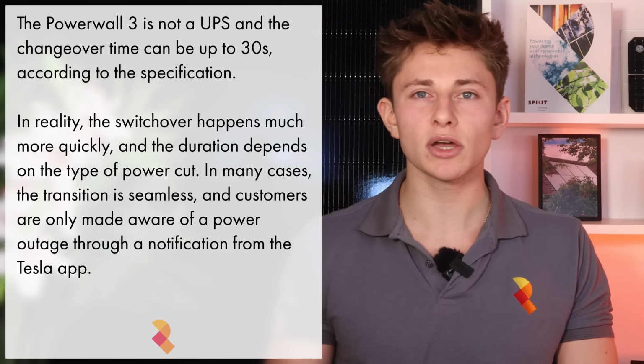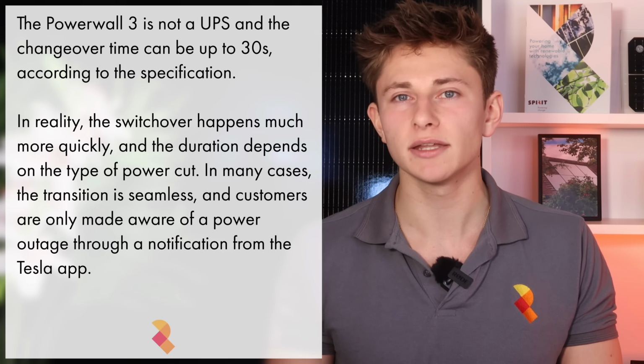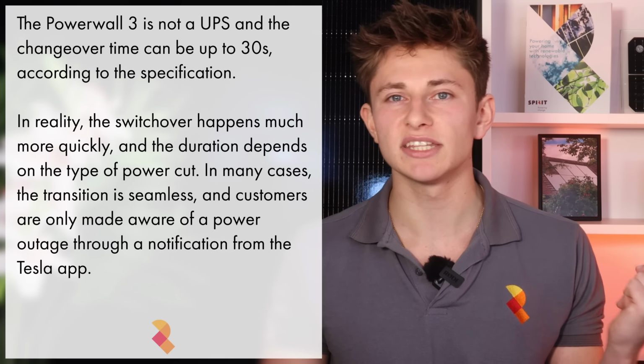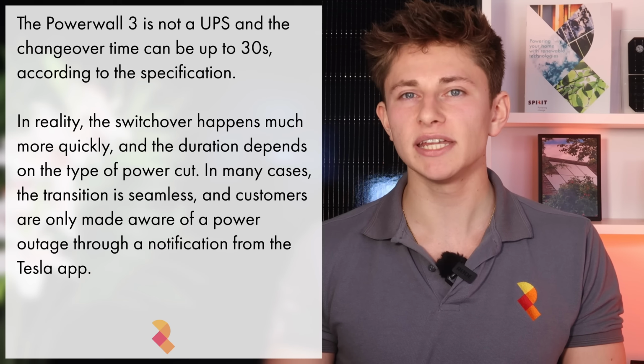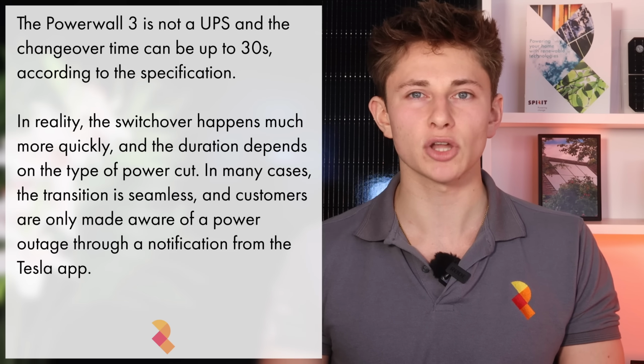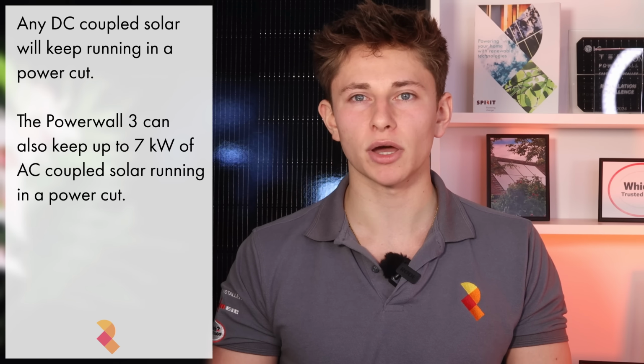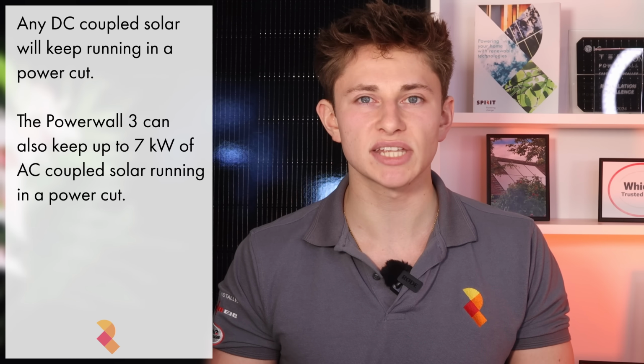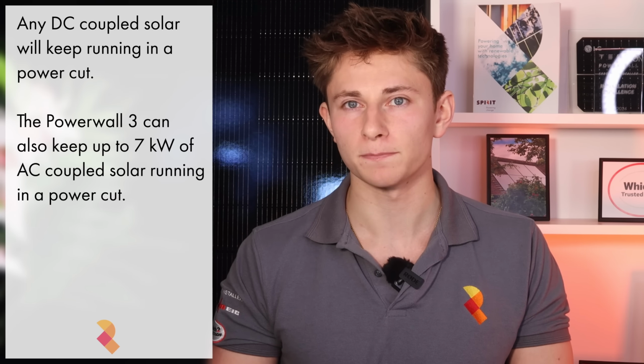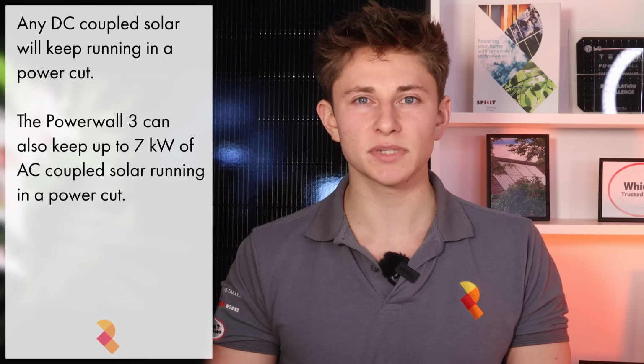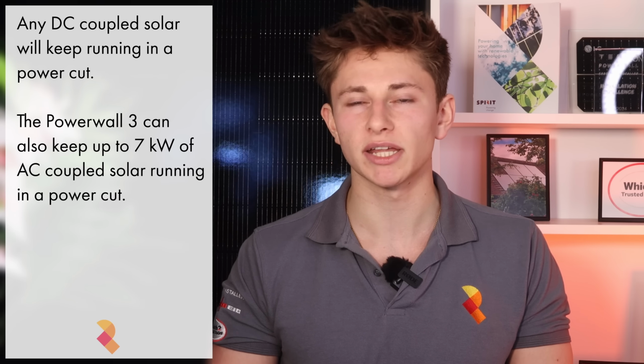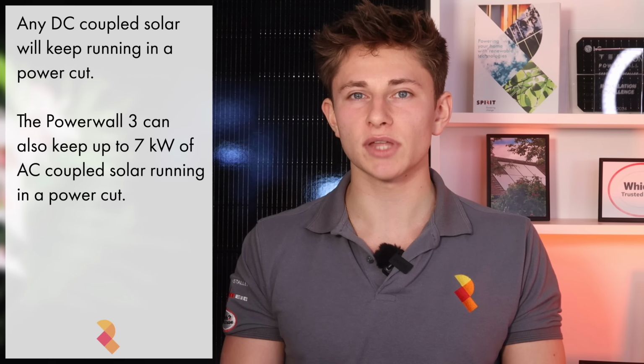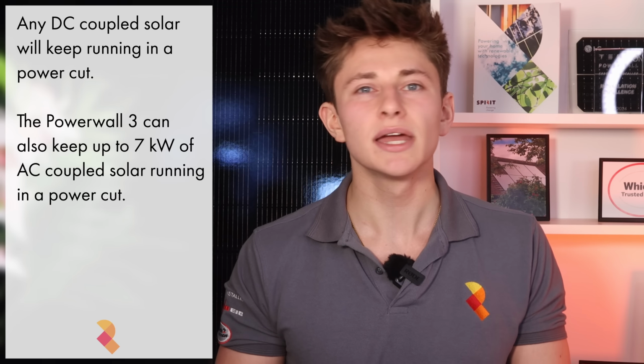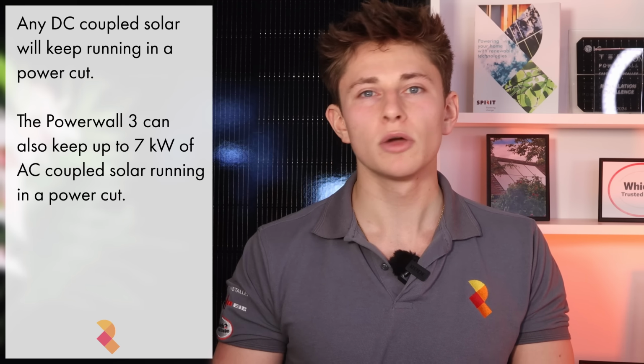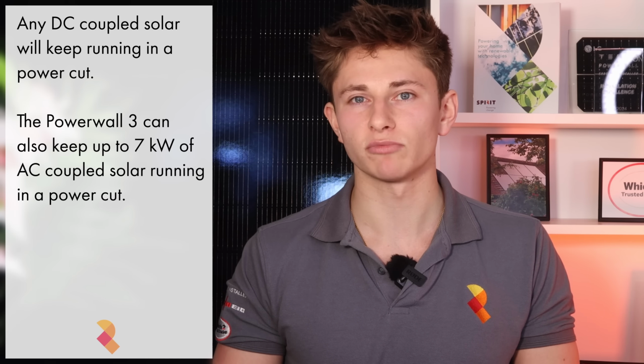For standard open circuit power cuts where there's a break in the grid line, the changeover time should be pretty much instant, and many of our clients say they only knew there had been a power cut because the app had notified them. All of the DC coupled solar will be kept running in a power cut, even if the kilowatt peak of the solar system is higher than the rating of the inverter. The Powerwall 3 can also keep up to 7 kilowatts of AC coupled solar running in a power cut. So any solar panels that are connected into a standalone inverter can be kept running in a power cut as well, without any rewiring of the existing system required.